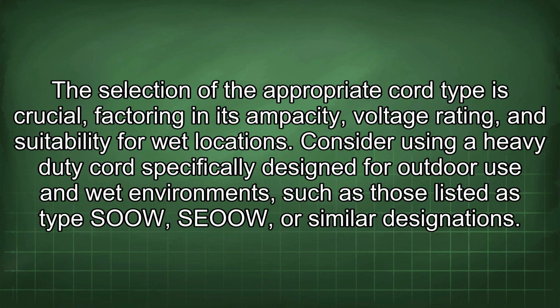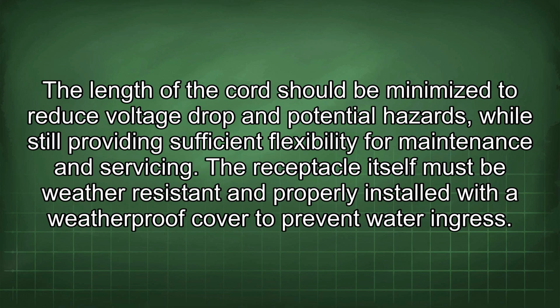The selection of the appropriate cord type is crucial, factoring in its ampacity, voltage rating, and suitability for wet locations. Consider using a heavy-duty cord specifically designed for outdoor use and wet environments, such as those listed as Type SOOW, SEOOW, or similar designations. The length of the cord should be minimized to reduce voltage drop and potential hazards, while still providing sufficient flexibility for maintenance and servicing.